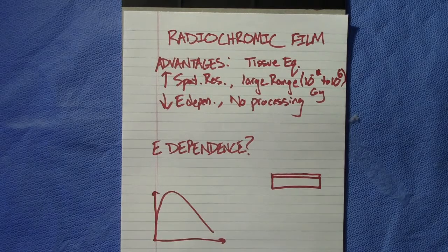Things like the orientation of the way the film is shot and scanned, the timing between when you do your calibration curve and your experiment, all these things, although seemingly insignificant and maybe you wouldn't think they would matter, play a big role in analyzing with radiochromic film. And so that is why I would do it myself. Even if you do have a guideline in the department, it needs to be very detailed and everyone needs to be on the same page to ensure that the film is properly calibrated and scanned in an accurate manner.